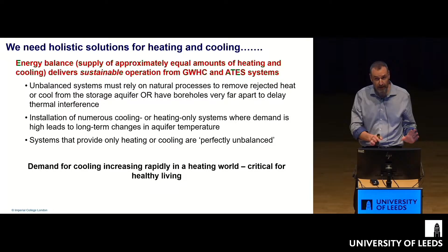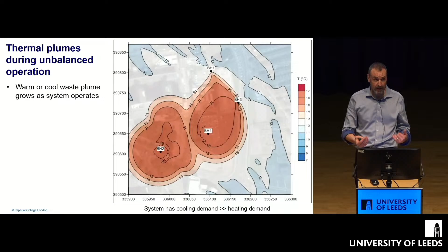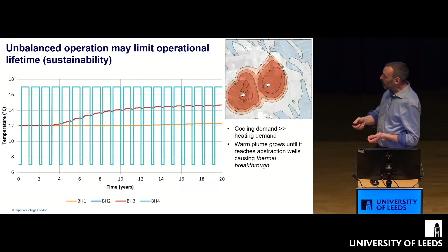Just to give you an example of what can happen if a system is very imbalanced - this is a system in Liverpool that was operating for a hospital, and the cooling demand was much bigger than the heating demand, so lots of waste heat has been injected back into the aquifer, causing a hot plume to grow bigger and bigger. If you look at the temperature of the boreholes as a function of time, this is what we're injecting - heat, a bit of cool, heat, and a bit of cool. So you can see we're unbalanced, injecting and rejecting more heat back into the aquifer.